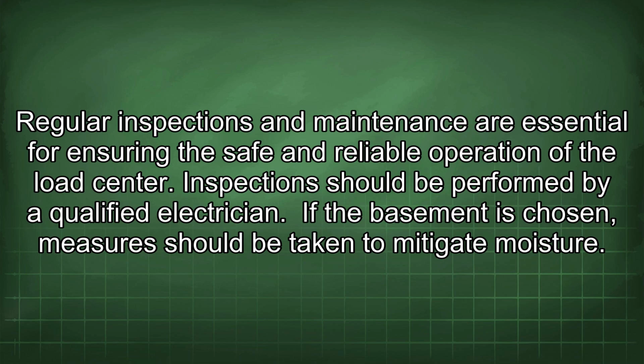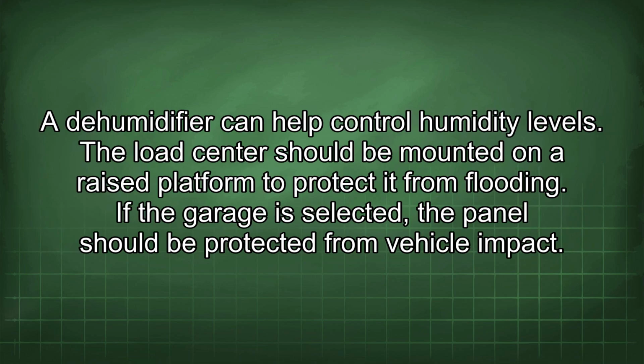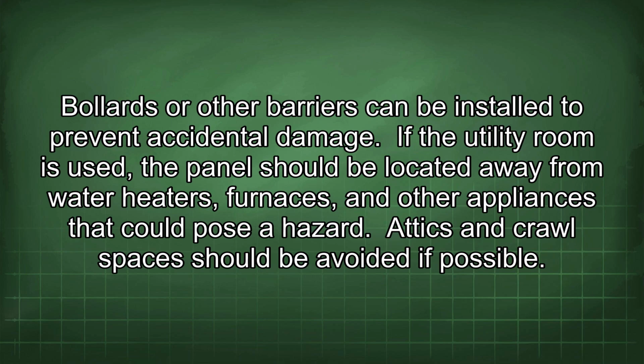If the basement is chosen, measures should be taken to mitigate moisture. A dehumidifier can help control humidity levels. The load center should be mounted on a raised platform to protect it from flooding. If the garage is selected, the panel should be protected from vehicle impact. Bollards or other barriers can be installed to prevent accidental damage.